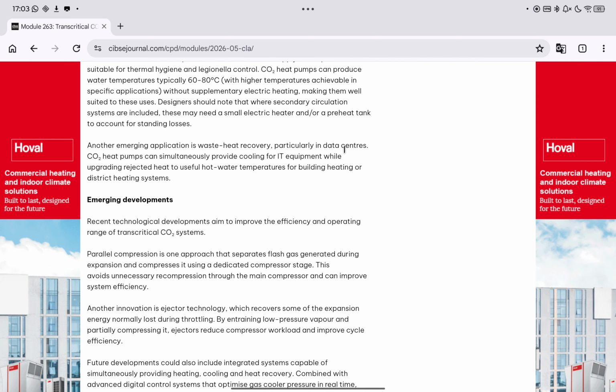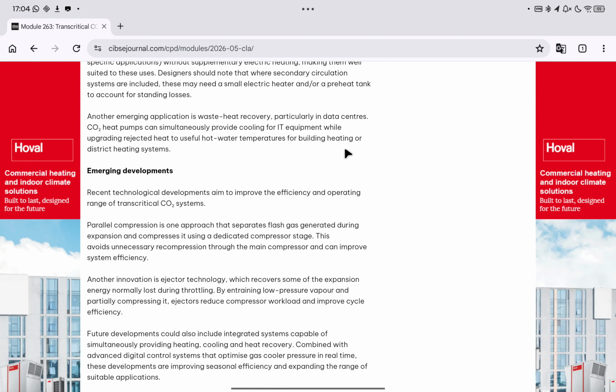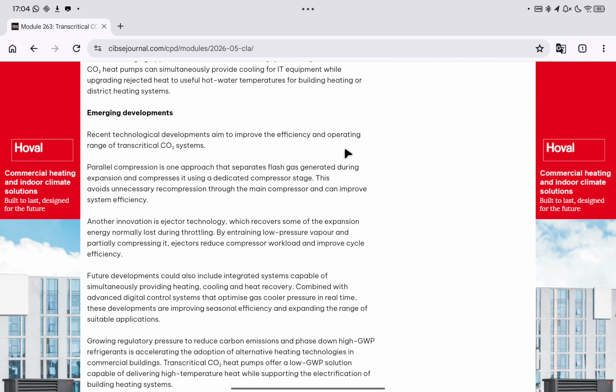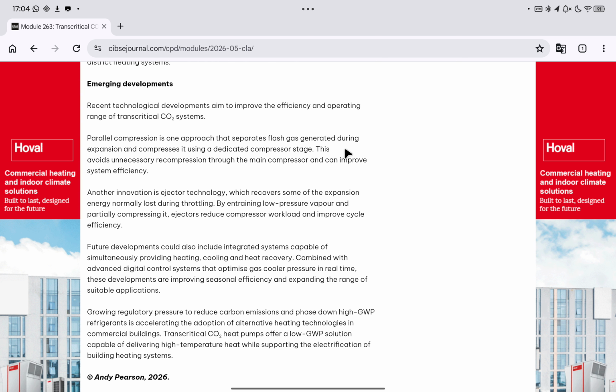Emerging developments. Recent technological developments aim to improve the efficiency and operating range of transcritical CO₂ systems. Parallel compression is one approach that separates flash gas generated during expansion and compresses it using a dedicated compressor stage. This avoids unnecessary recompression through the main compressor and can improve system efficiency. Another innovation is ejector technology, which recovers some of the expansion energy normally lost during throttling. By entraining low-pressure vapor and partially compressing it, ejectors reduce compressor workload and improve cycle efficiency.